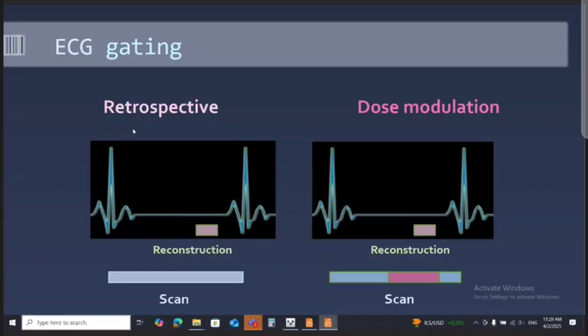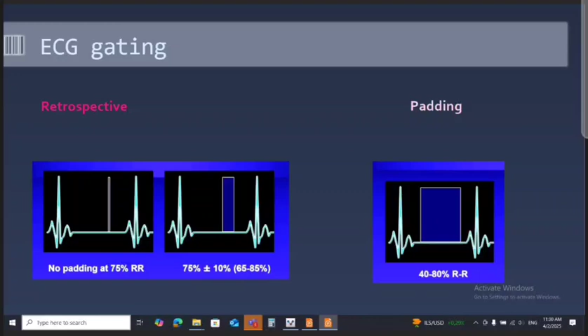On the other hand, the prospective images, which were initially performed at a single point of the RR interval, the condition was dealt with by increasing the width of the acquisition by padding. In this case, the prospective with padding, we have a wide window of imaging from 40 to 80% of the cardiac cycle, but outside this window, there is no acquisition. And in this case, we cannot perform cardiac function analysis, but we can have images at the systolic and diastolic phases of the cardiac cycle, so we can interpret the coronary arteries at systole and diastole. The prospective imaging with padding, a widening of the window, also allowed for reduction of the dose as compared to the retrospective imaging.